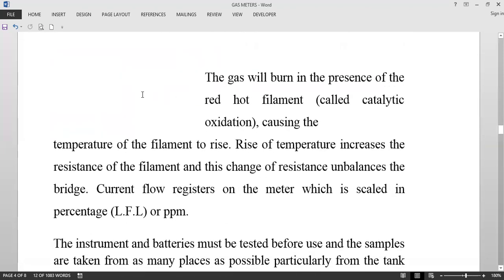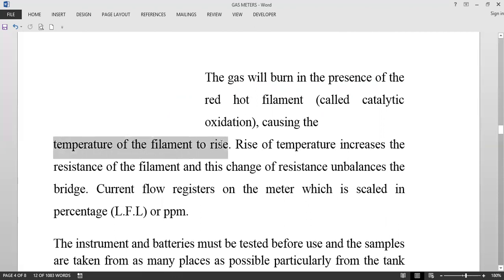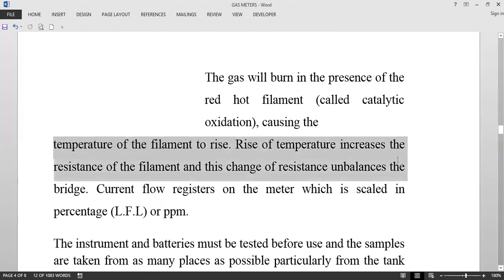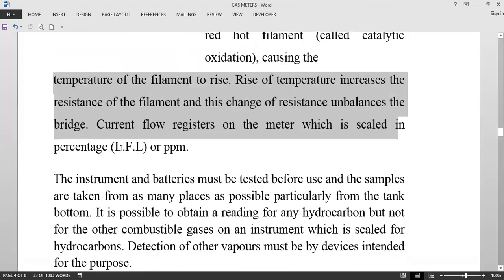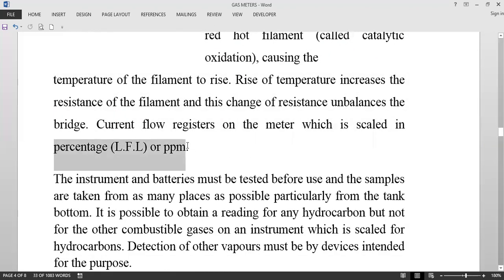The gas burns in the presence of a red-hot filament. This process is known as catalytic oxidation. It causes the temperature of the filament to rise, which increases the resistance of the filament, and this change of resistance unbalances the bridge. The current flow registers on the meter, which is scaled in percentage of lower flammability limit or parts per million.